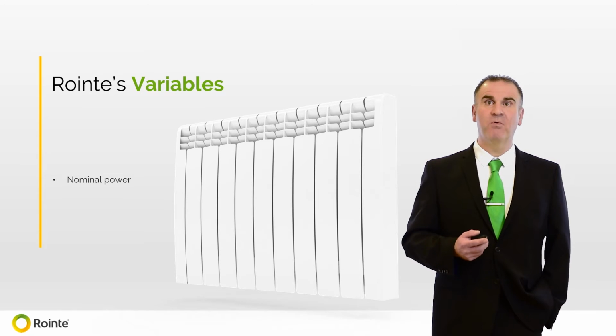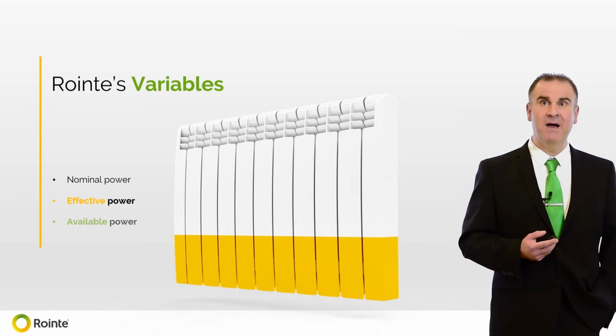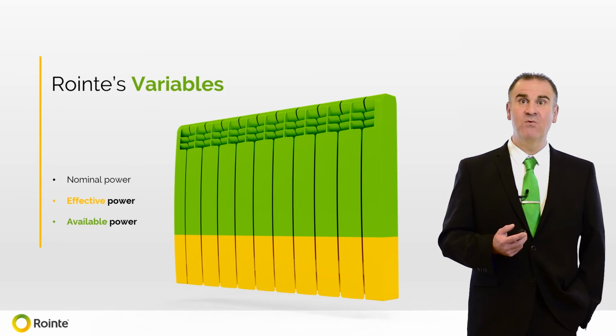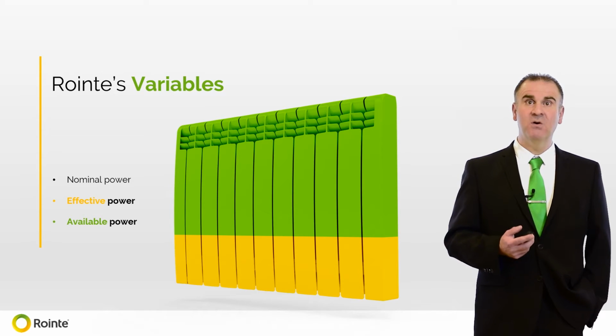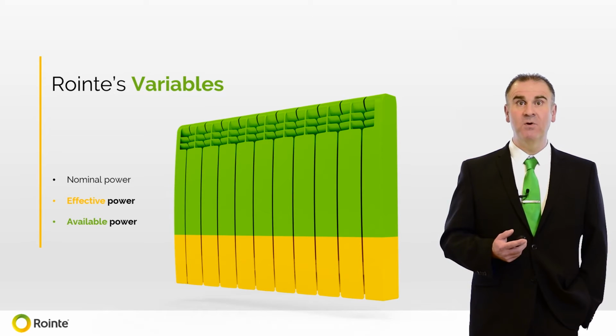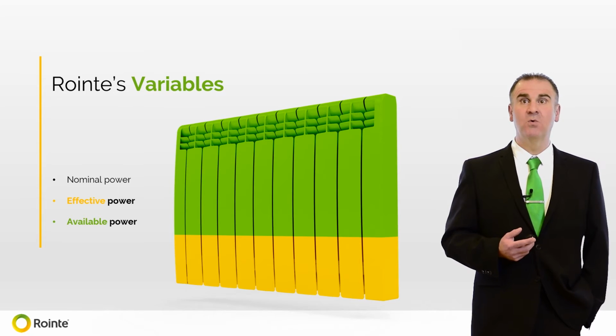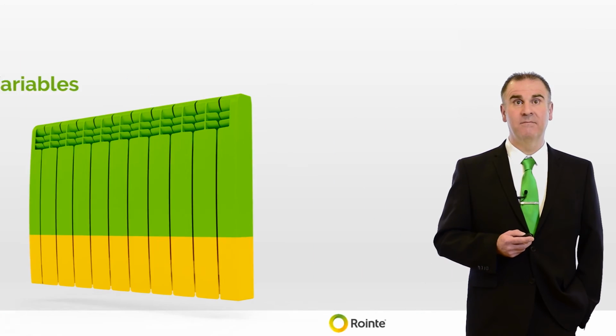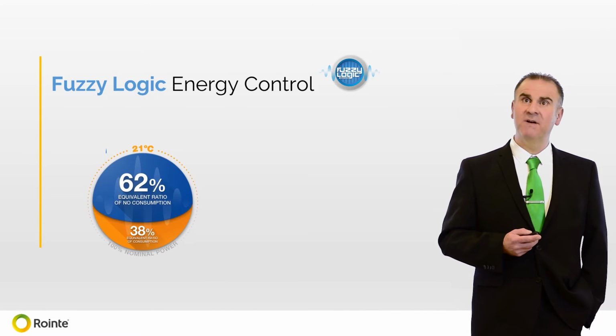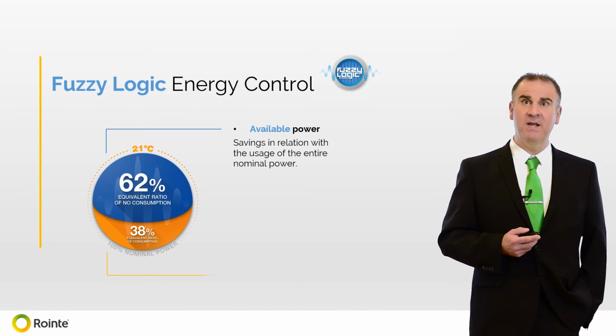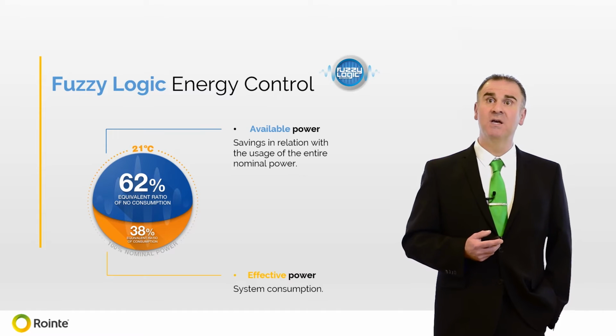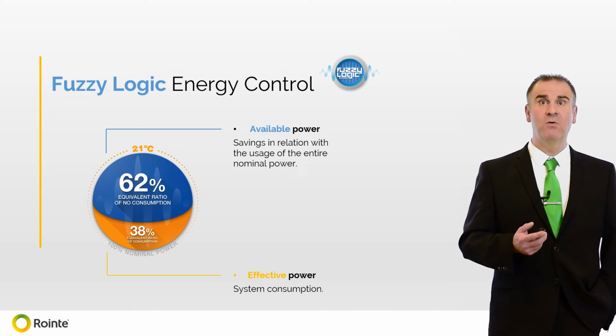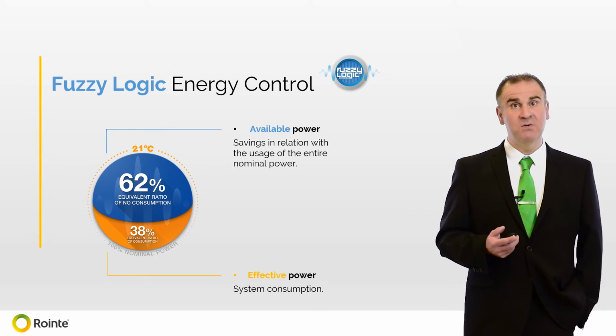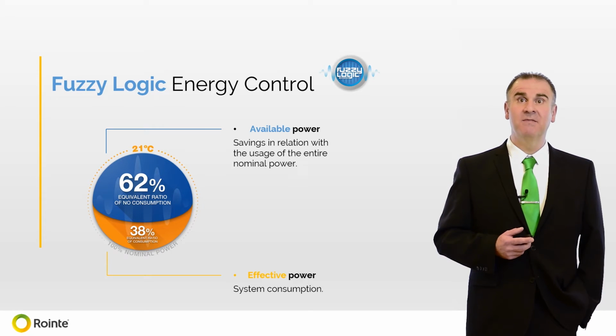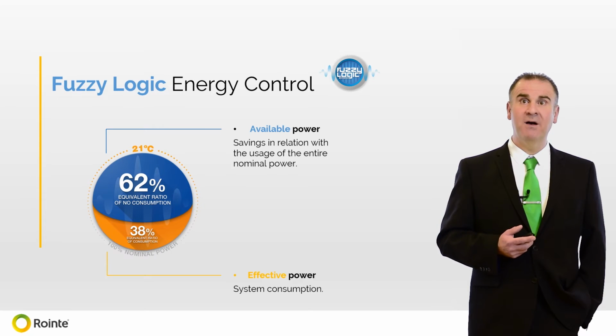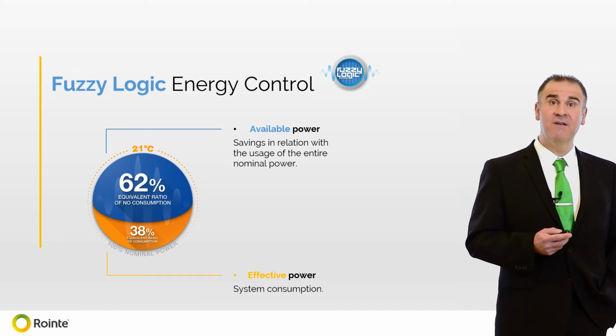The energy usage of a product is calculated using the effective power, which is the power it uses in real time. The power that is not used, i.e. the difference between the nominal and effective power, is called the available power. With our fuzzy logic technology, at 21 degrees, our radiators typically use just 38% of the nominal power, and therefore do not use 62%. This calculation can be used to work out energy usage over a given period.